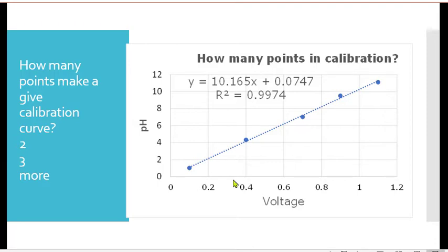So the problem is, if you read at these different voltages and you say all I need is one voltage and get the corresponding pH or at least two to do a calibration curve, you might be incorrect. I'm going to show you what would happen. Let's say we chose this point right here and we chose this point right here. We're just going to use those two points. You could see that the calibration curve that would be set up across those two points would be an error.